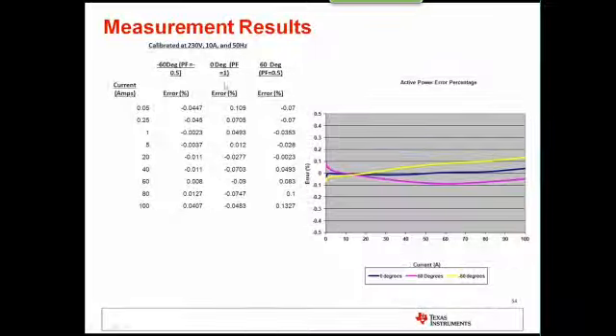We also inject 0 degree and negative 60 and 60 degree phase shifts, so positive and negative, where we have the current leading or lagging. This can be difficult for some meters to measure, and we can still hit the same accuracy requirements across the full spectrum. 0.2%, yeah, 0.2%.